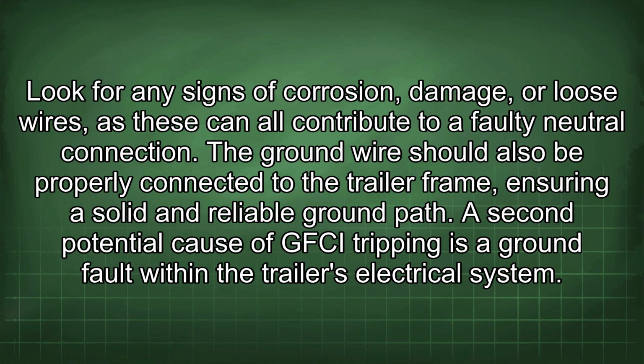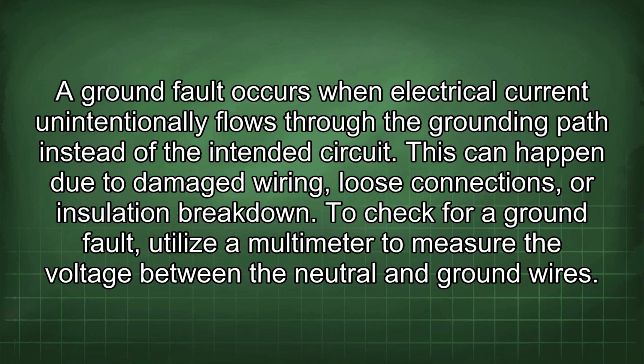A second potential cause of GFCI tripping is a ground fault within the trailer's electrical system. A ground fault occurs when electrical current unintentionally flows through the grounding path instead of the intended circuit. This can happen due to damaged wiring, loose connections, or insulation breakdown.